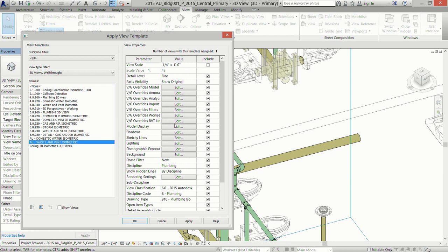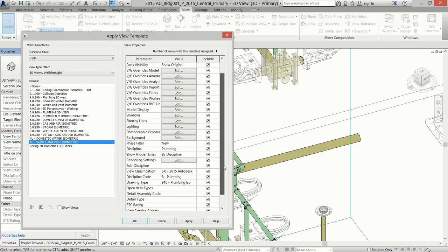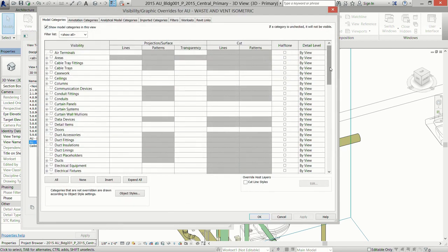We set the detail level to Fine. For visual display, 'Hidden Line' works best — it picks up the colors you set in your filters. 'Realistic' picks up the material and does not print well at all; I would highly recommend keeping this setting at Hidden Line no matter what. We also create our own drawing type for plumbing isometrics — we separate them from plans and sections and give them their own number because we use them so heavily.